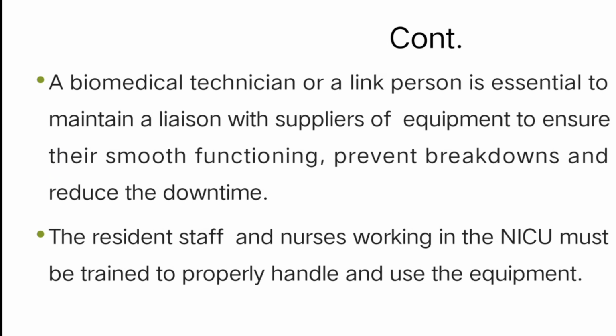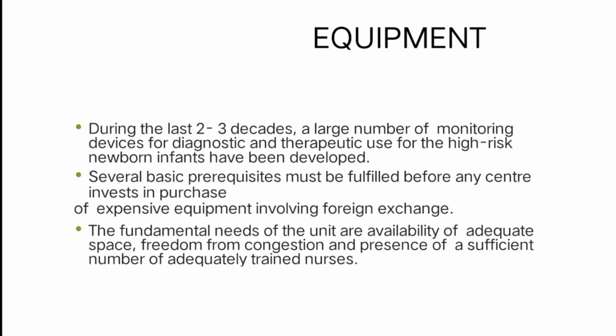A biomedical technician or a link person is essential to maintain a liaison with suppliers of equipment to ensure their smooth functioning, prevent breakdowns and reduce downtime. The resident staff and nurses working in the neonatal intensive care unit must be trained to properly handle and use the equipment. So a multi-specialty hospital investing in equipment should give proper training to the nurses, and the biomedical technician should also be present in the hospital to see to any failures in the equipment, for its smooth functioning, or if the equipment requires decontamination. Everything should be carried out in the hospitals.